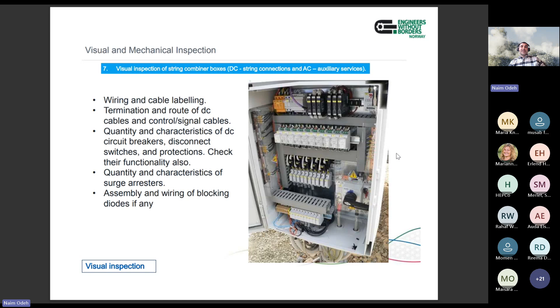This is inspection for the DC and AC auxiliary systems. This is not necessarily there in all projects, but such enclosures are there in some of the projects. If they are there, it's important to check the breakers, cable arrangements, cable terminations, cable tags. All cable runs should be as per the design, and the tags and labels as per the design. For other electrical equipment, here we mean the switchgears, the transformers, and so on, also check the wiring labeling, check the connections if they are done in the proper way, if they are as per the design, check the breakers if they are functioning well, and so on.